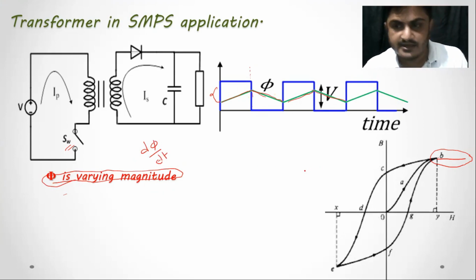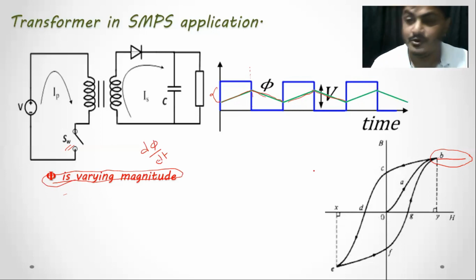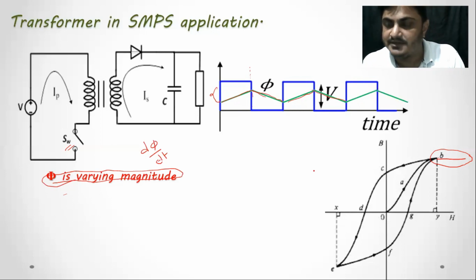Even if you have an AC transformer, if you connect it with a DC supply at your home and are able to disconnect that supply within the time limit, before it reaches saturation, then you can connect the transformer with DC supply. But remember, you cannot do this, because you don't have the capability to disconnect the supply within a few microseconds.